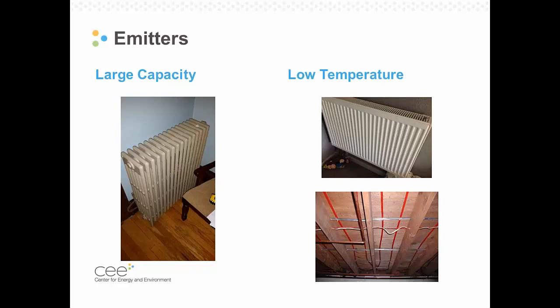So houses over time have improved. We've done small levels of insulation or air sealing. Our boiler efficiency in general has gone a lot up. A lot of these radiators predate even our 80% efficient boilers, and so they had much less efficient boilers when they were installed. And so all these things, over time, have made these boilers more and more oversized. And so luckily, I guess the housing stock in Minnesota allows us to run a lower than designed water temperature through these boilers and still meet the loads of the home.